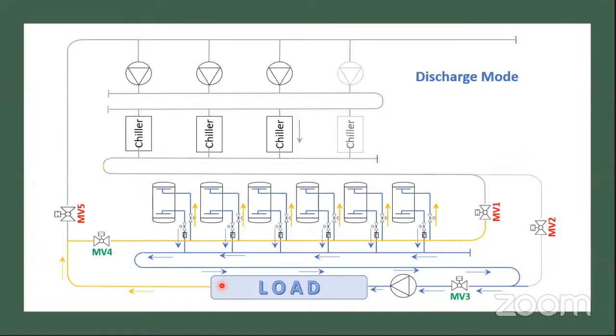This is the emergency mode in which there is a power outage and the chillers are stopped. As you can see, the chillers are stopped and there is a need for thermal energy storage to discharge. In that case, only the secondary pump is drawing the chill water from the bottom of the tank, sending it to the load for the time duration it is designed for, and this warm water is then coming back to the top header and going back to the thermal storage tank. And right when the chillers have come back, they have ramped up to full capacity, and the DG also came back.